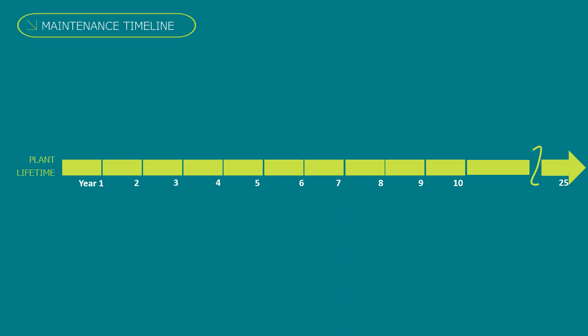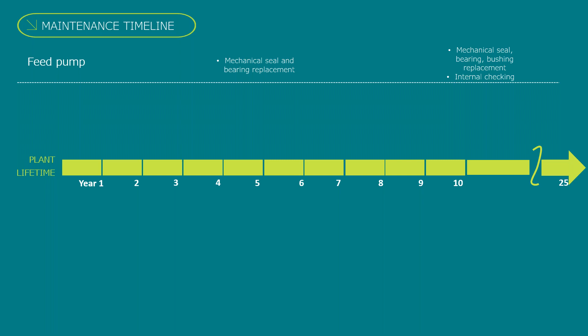Then I want to give an overview of the main appointments of the maintenance along the plant lifetime. The plant is designed for more than 25 years, and starting from the mechanical equipment, the feed pumps basically only need the replacement of mechanical seals and bearings, which are the wear parts, after 5 years, and an additional check of the internals after the 10th year.